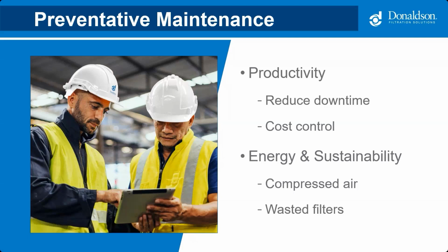Secondly, energy and sustainability have been a hot topic in the industrial manufacturing space for a while now, and it still is. A poorly maintained dust collector is going to use more energy than it's supposed to. If you have plugged filters, now your pulsing system is going to be working too hard, as well as your fan. So now you're wasting compressed air. If you haven't properly maintained your pulsing system, it could be leaking, also wasting compressed air.